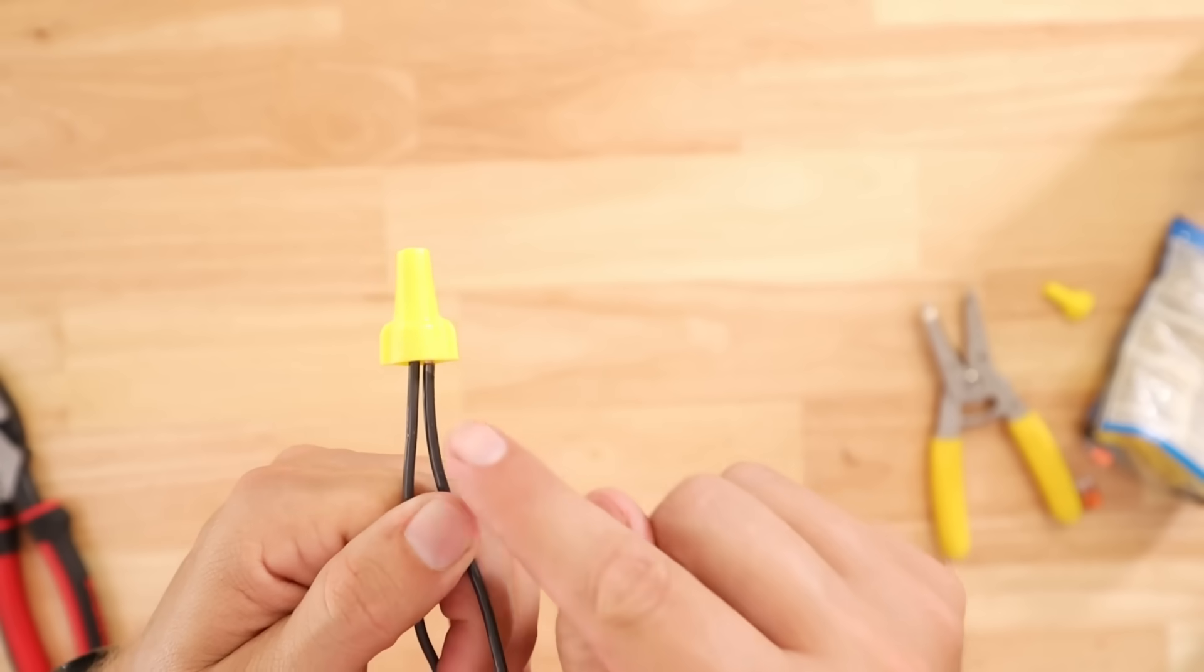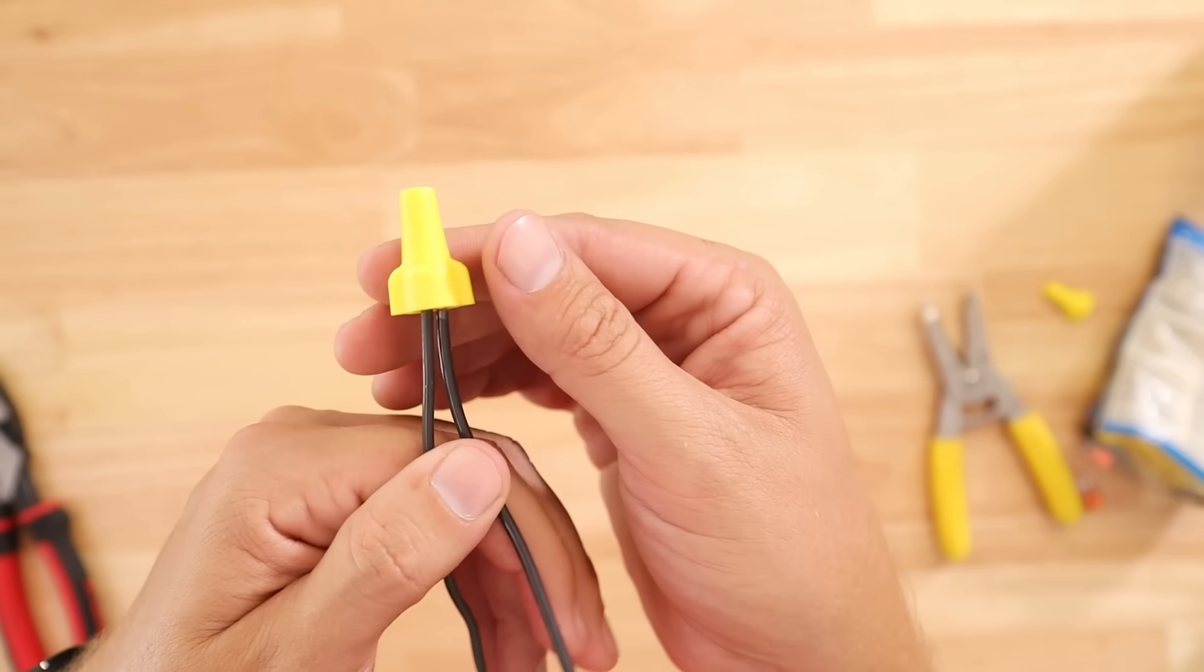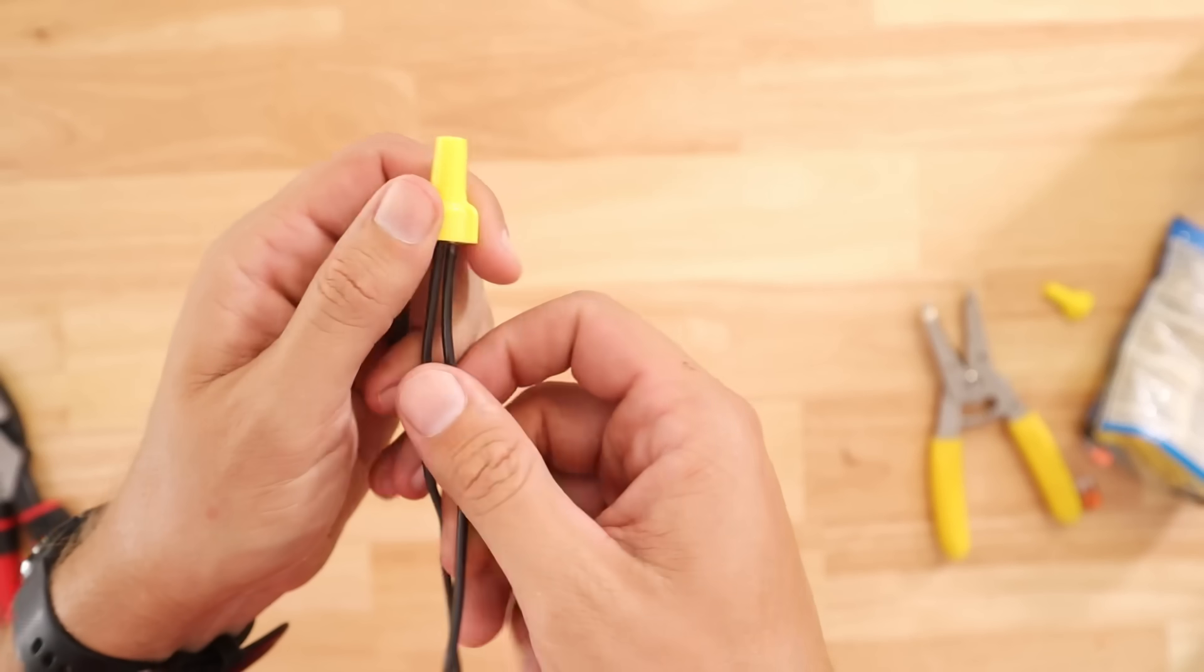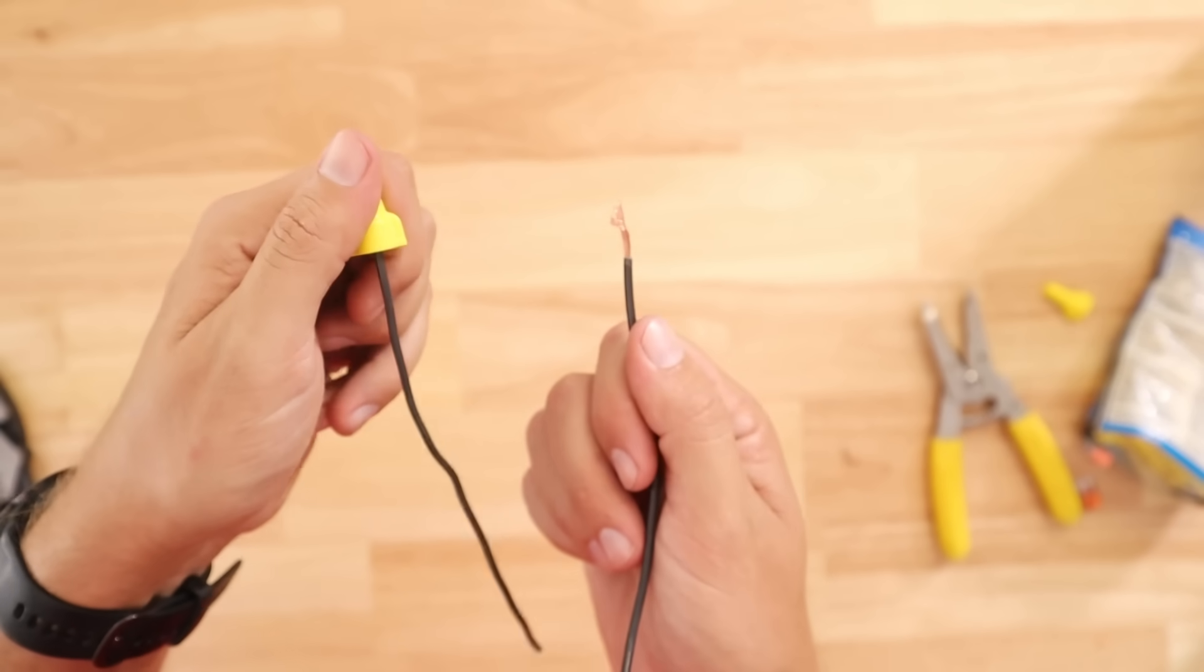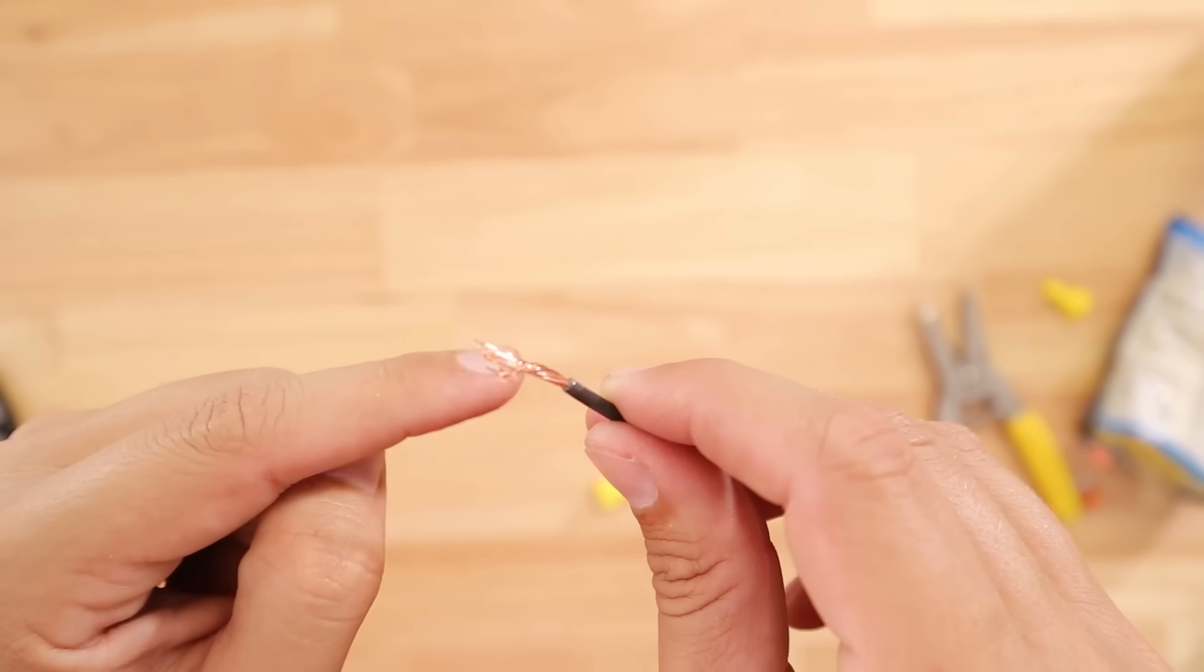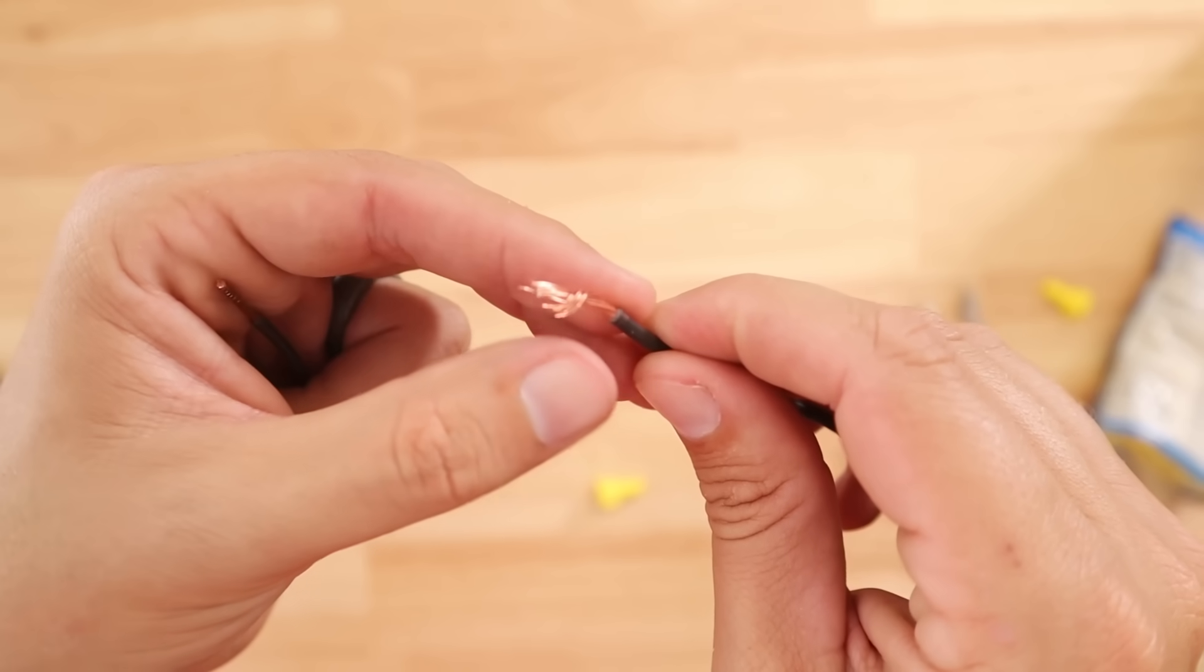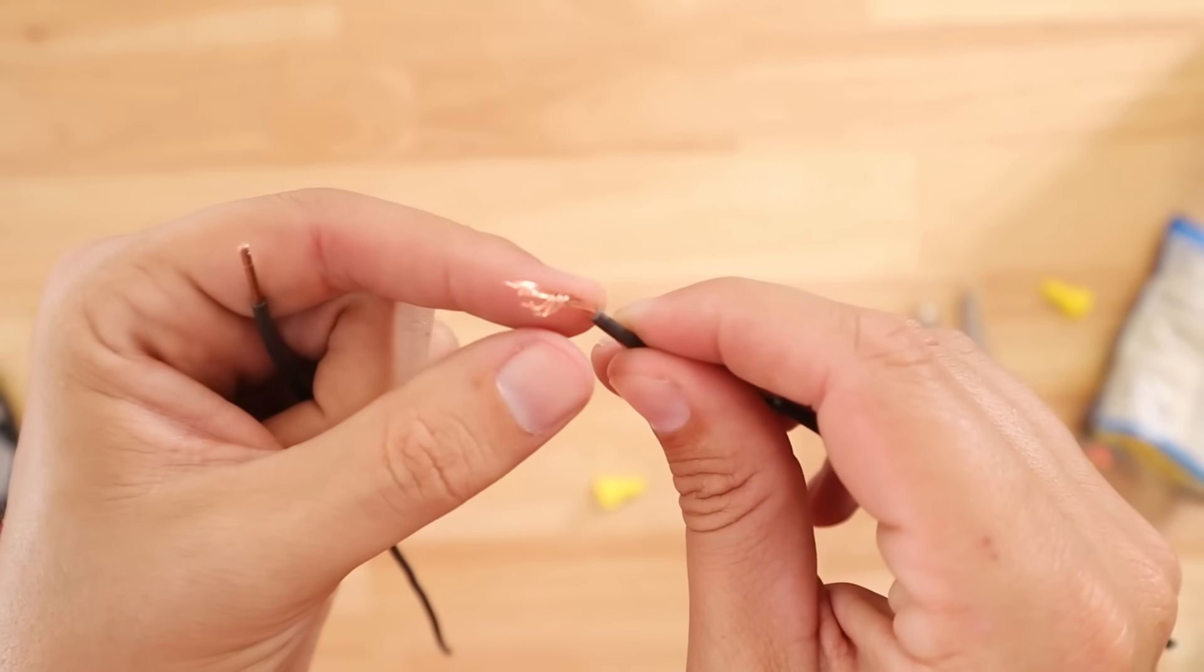And also what can tend to happen especially using stranded wire is it's not going to hold as well in a wire nut. It didn't take a whole lot of force to pull that out. And as you can see in this particular case just like with the solid core when you don't turn it enough we barely got that stranded wire to start wrapping around this solid core wire.